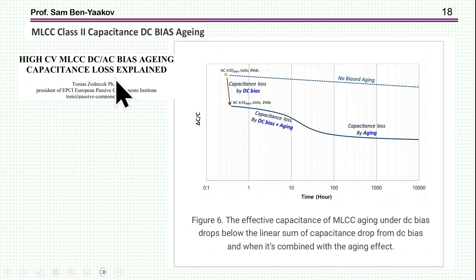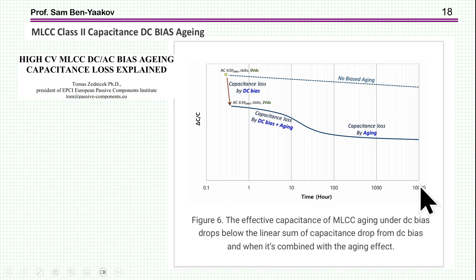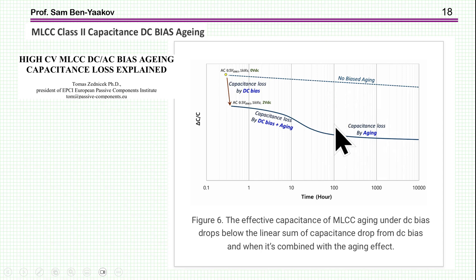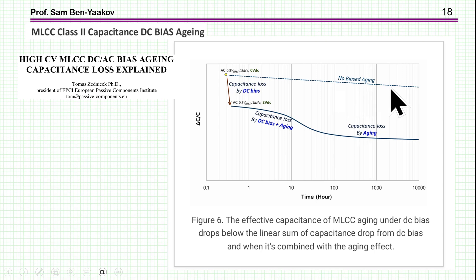There is some good news from another pioneering paper. When measurement is carried out to up to 10,000 hours with DC bias, the aging starts with a certain slope, then tapers off, and the rate of change eventually meets that of no DC bias. So the initial drop is due to the DC bias effect — which we recognize — but for longer time, we are back to the normal rate of aging. However, this is one paper and one experiment, and it's unclear how well it represents all capacitors being produced.